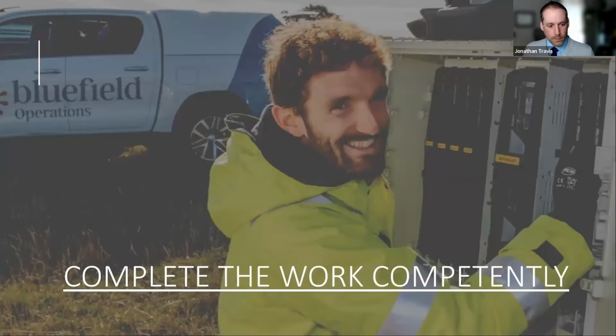And the last piece, and I touched on this earlier, but when you look at the workflow, you go through that safety piece first. Maybe you get it de-energized, or maybe you're doing the testing and troubleshooting, or maybe you've gone through the energized work permit. Well, you still have to complete the work competently. So that element doesn't go away. You've achieved the safety portion of the work, but if you make a mistake in the technical or the hands-on part, you can now create an arc flash or a shock hazard or something like that.